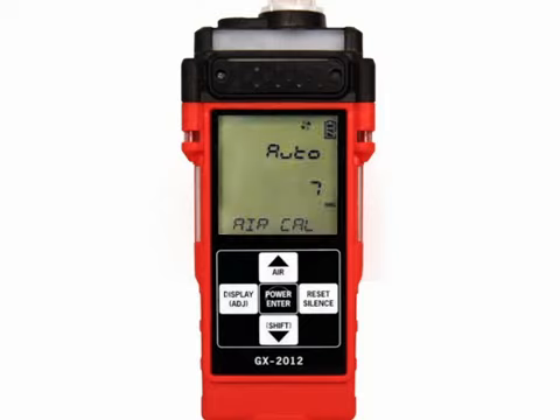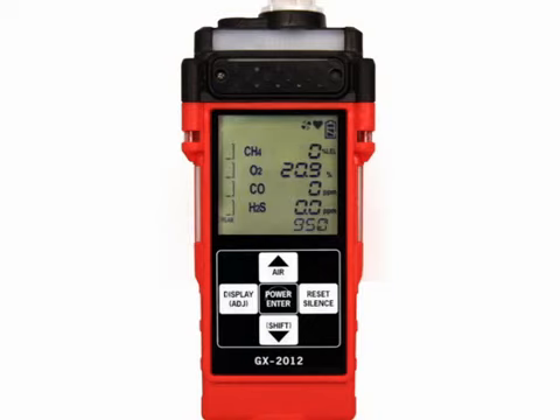If the Auto Zero adjustment function is turned on, the GX-2012 will automatically perform a fresh air adjustment at the end of the startup sequence. Make sure that you are in a known fresh air environment free of combustible or toxic gases and of normal oxygen content, which is 20.9%. If the fresh air adjustment is successful, the unit will proceed to normal measuring mode.